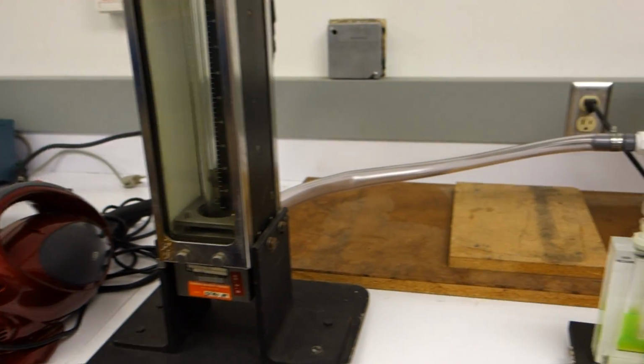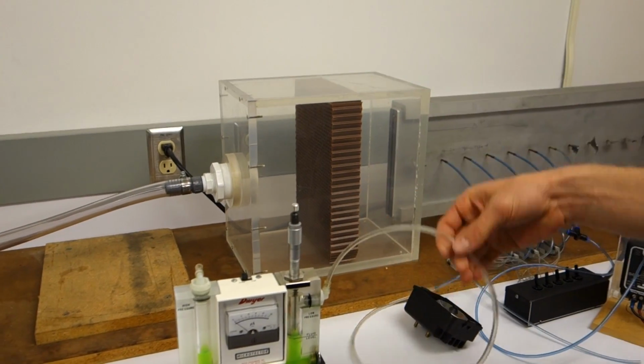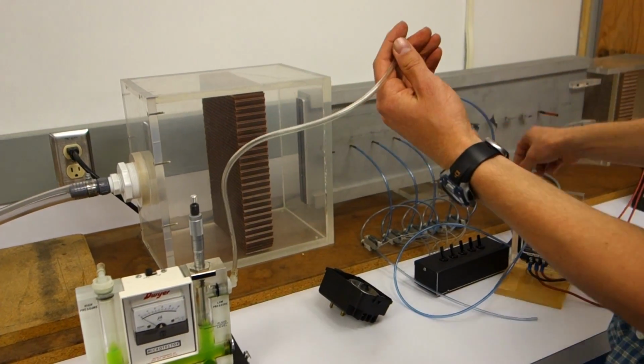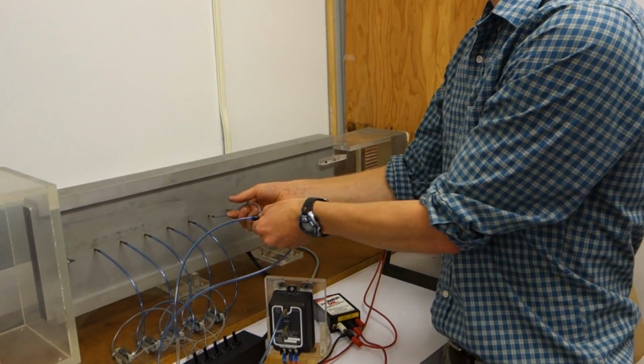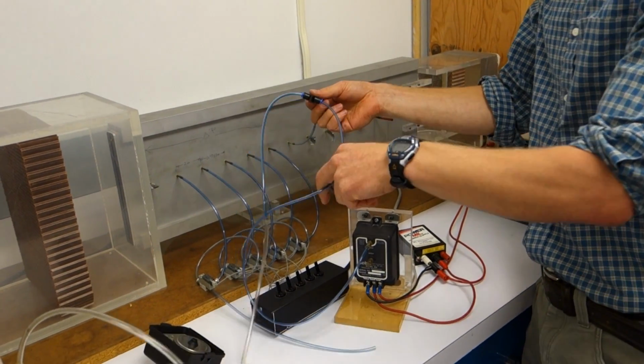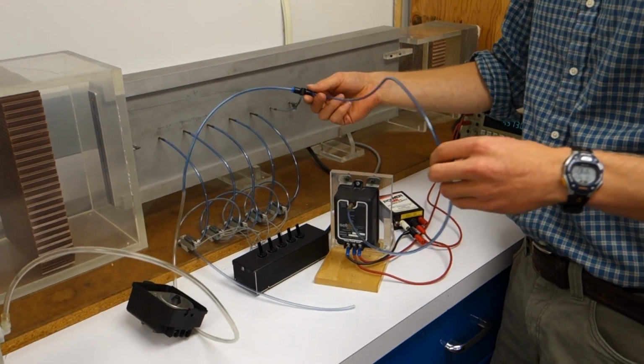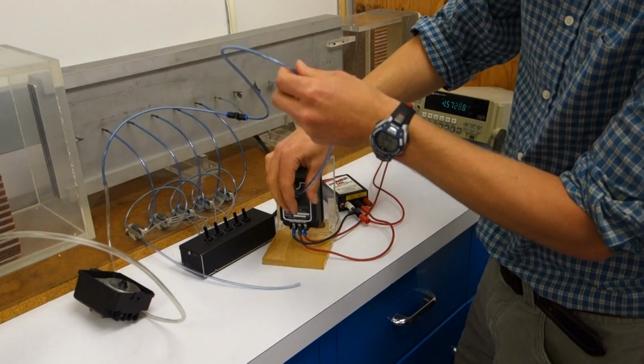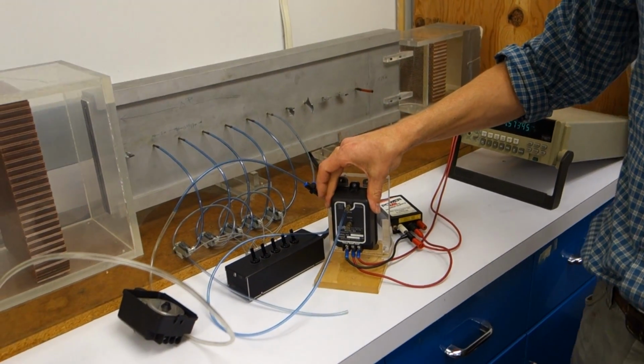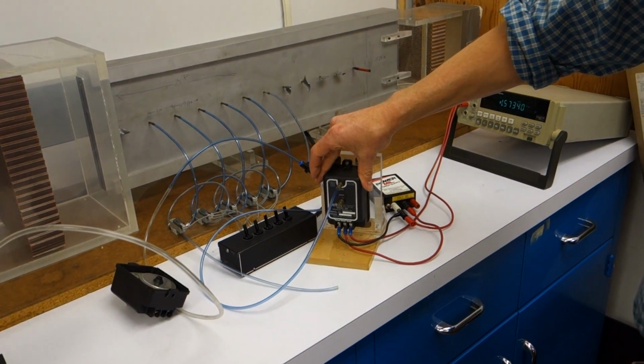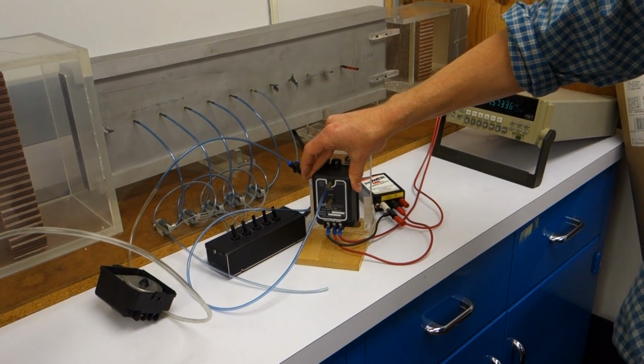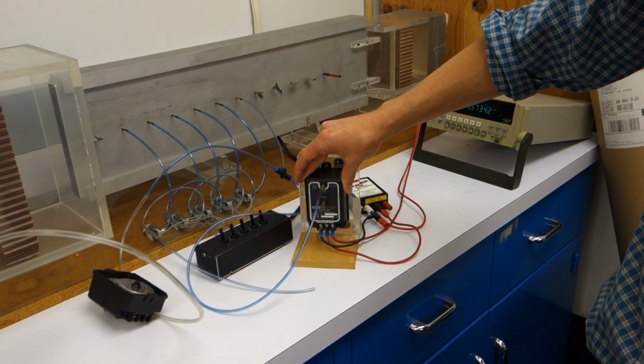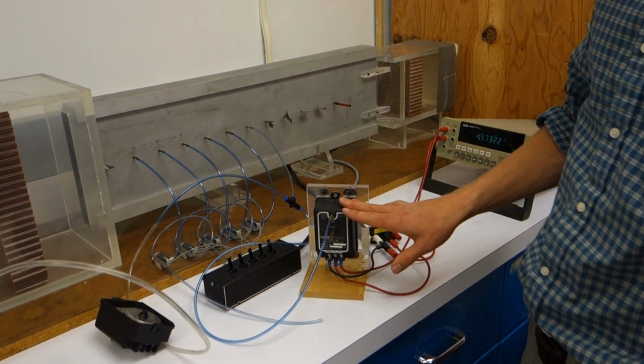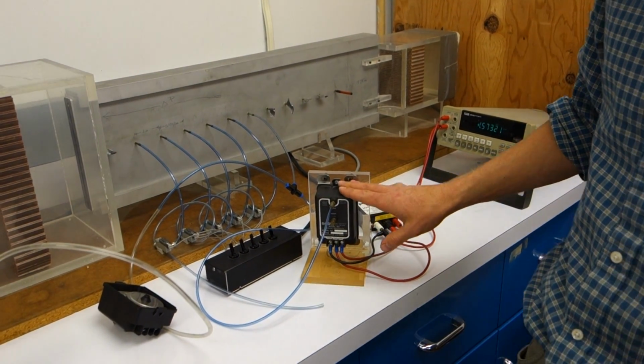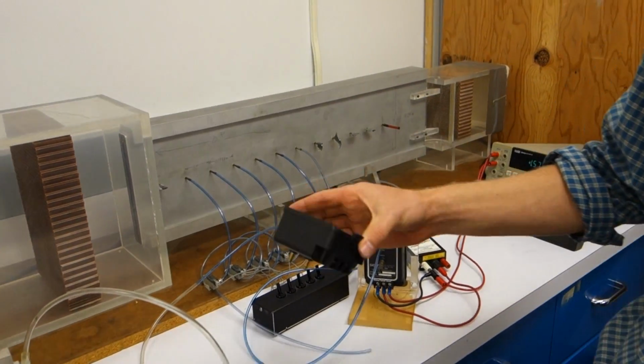So the way that we're going to use this is we're going to have one end connected to this tap in the duct. The other end of the tap is hooked up to this black box. This black box is called a capacitive pressure transducer, and it's electronic, so we're going to be able to take measurements electronically. And the way this works is it uses capacitance to sense pressure.